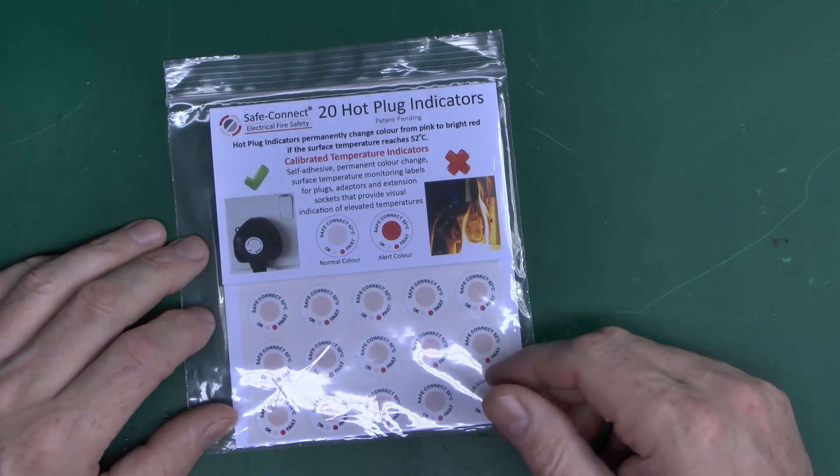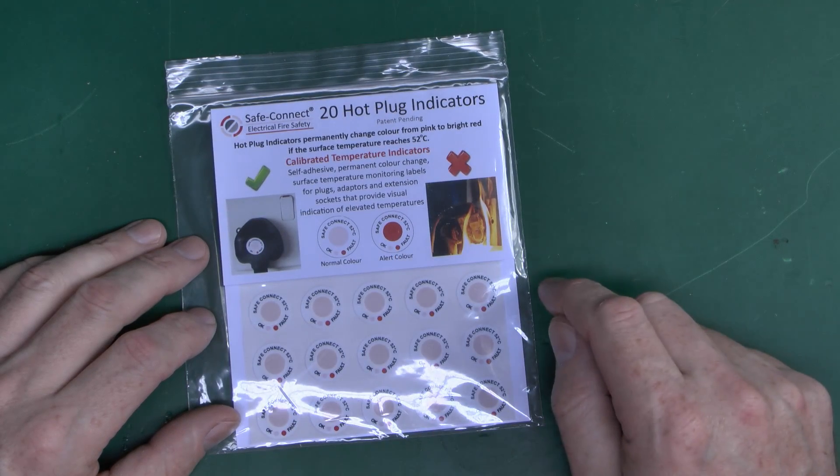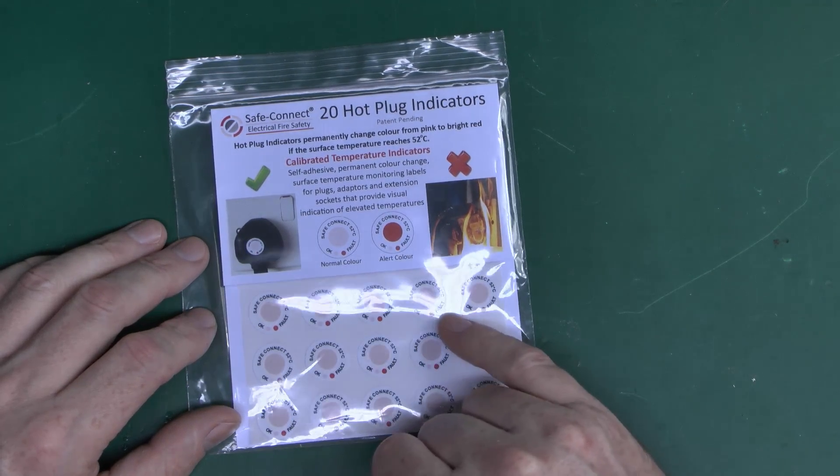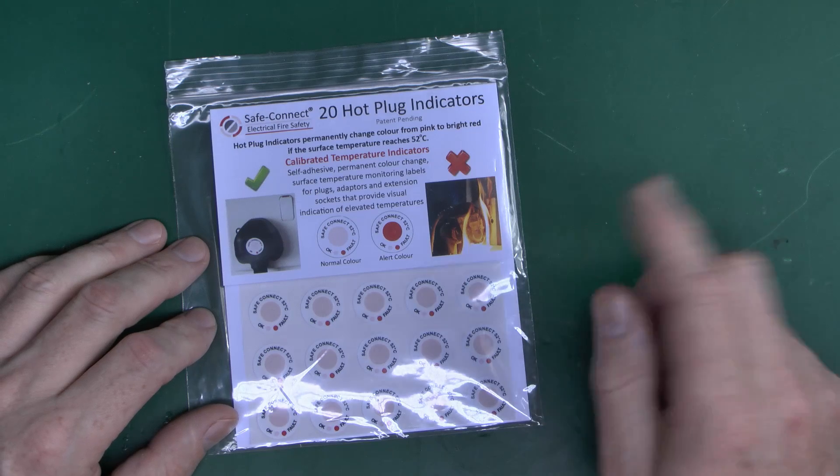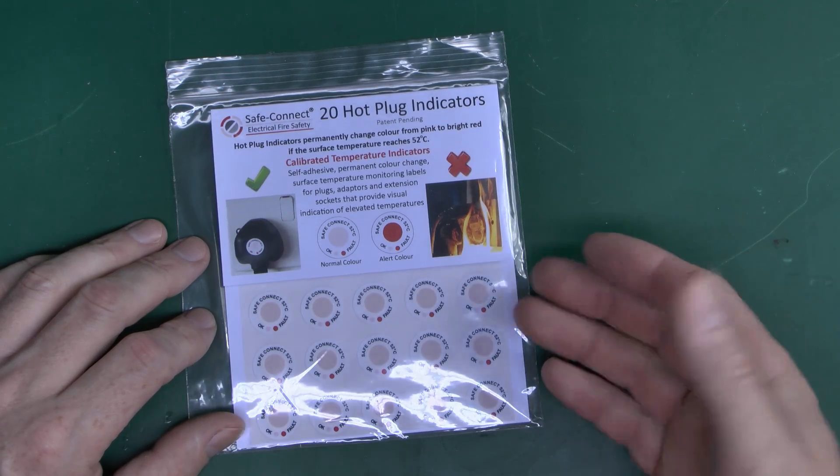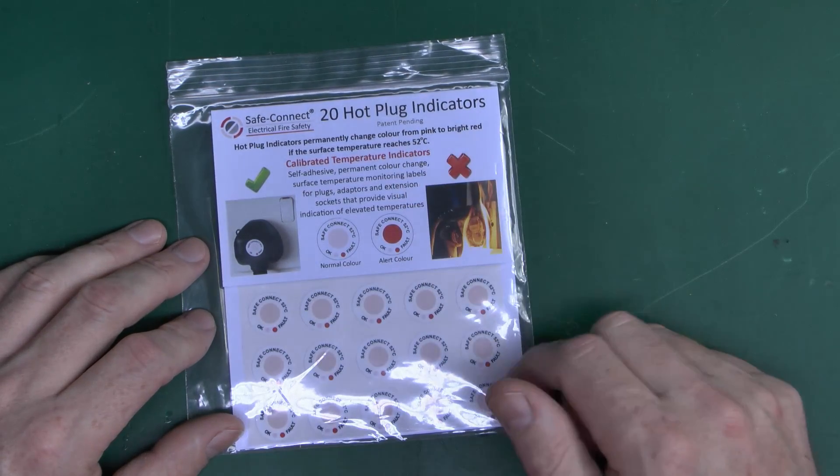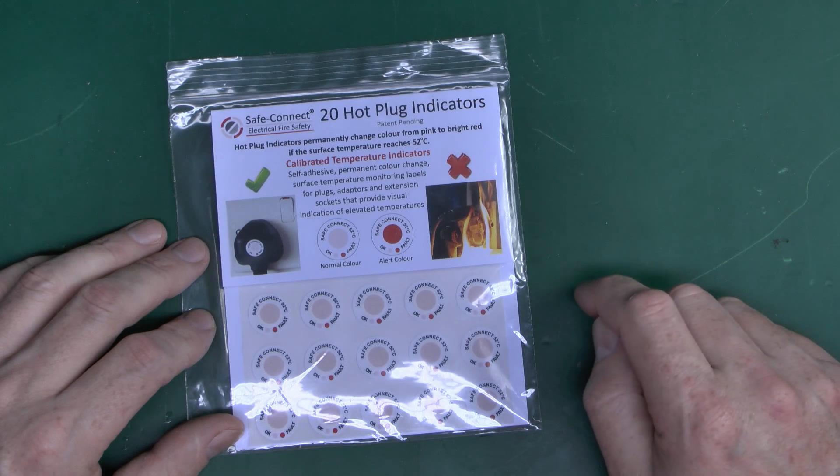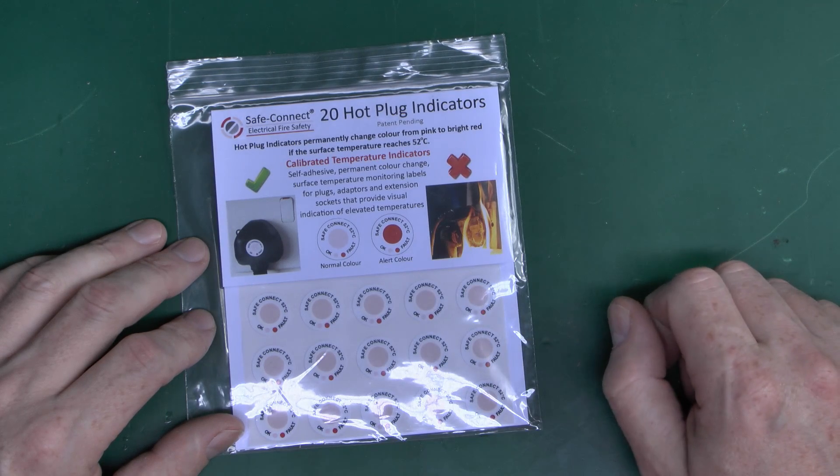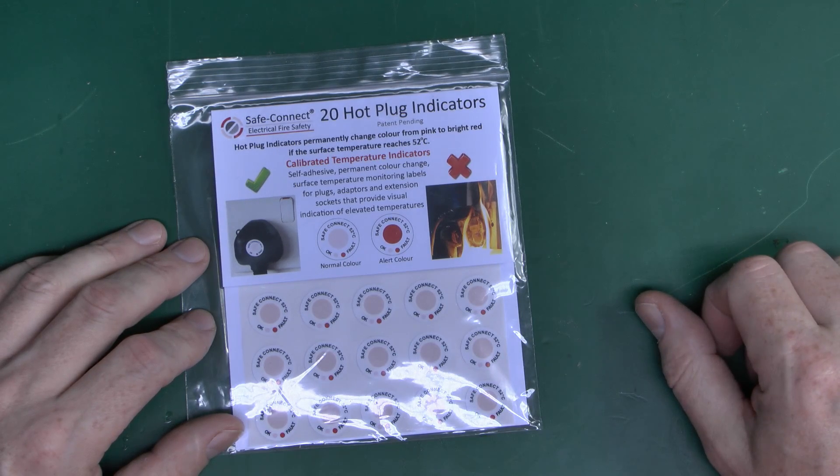Now these are relatively simple things. They're actually thermally activated labels, and in their supplied state the middle is a light pink color. The idea is that when these get hot, in fact over 52 degrees centigrade, then the middle turns red, and most importantly it stays red permanently even if the temperature then decreases afterwards.